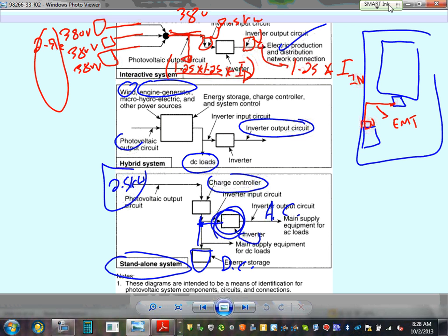What is it required to have? You need conduit protection. It doesn't have to be EMT. You can use PVC, Schedule 80. You can use EMT. You can use rigid. What they don't want you to use is a cable. Why? Because if you put a conduit here, the conduit will protect your conductors. Remember, these conductors don't have a whole lot of protection. If you put them in a conduit, the likelihood of damaging the conductors is much less than if they were just an SE cable, for example, coming down, all the way to the disconnect, right next to the panel. They protect them. Good point.